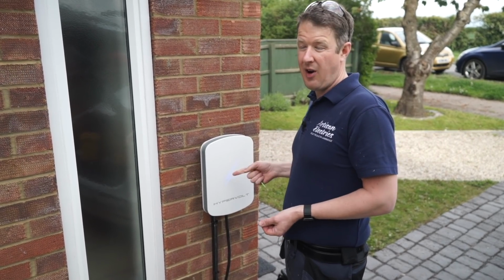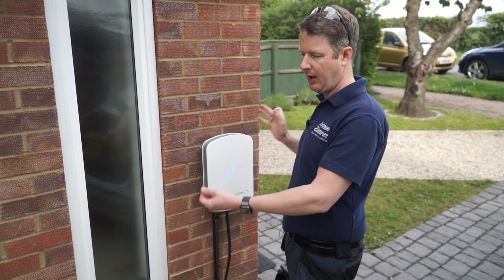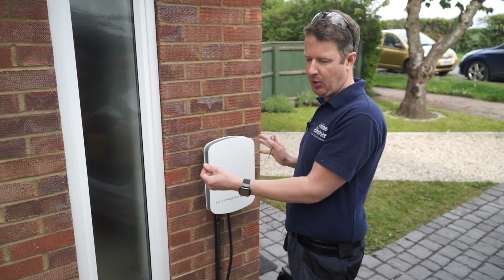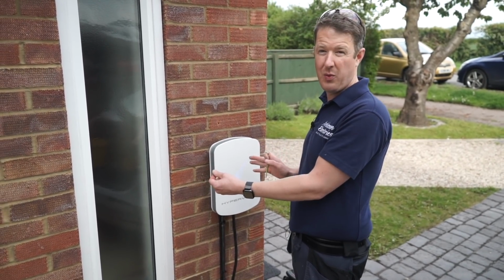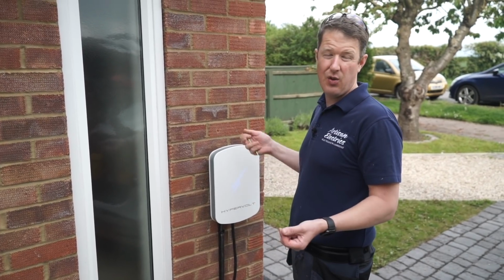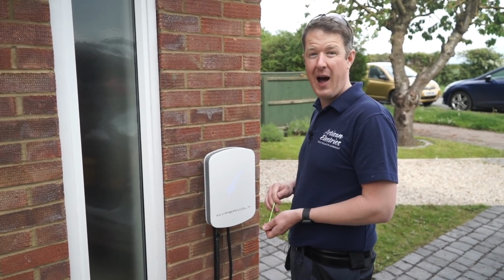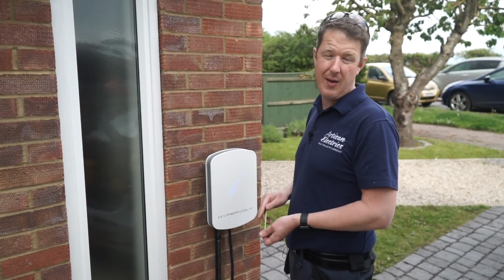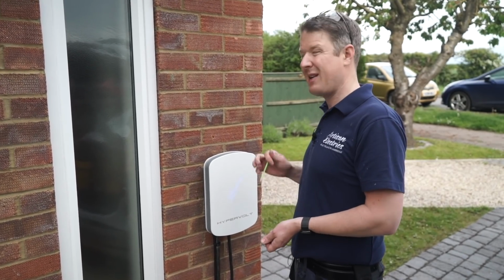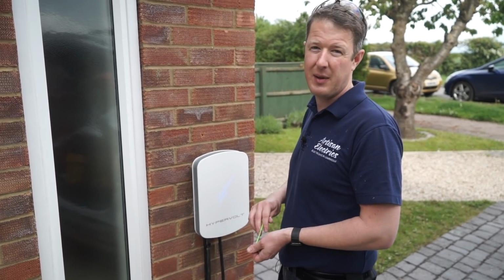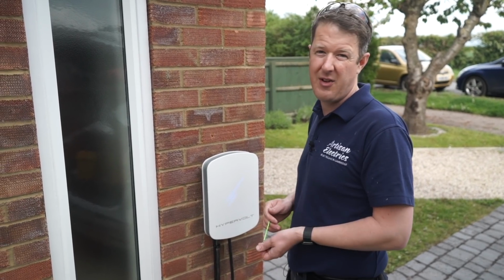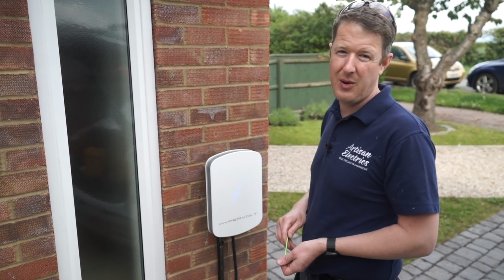Or you could just run it off, for example, a double stack Hager board, a dual RCD Hager board with type A RCDs in, then you could run it off an RCD way within that board, off a 32 amp circuit breaker. They do recommend a type C circuit breaker if possible, because of possible inrush current from the vehicle, but you can run it off a type B as well. It's not the end of the world.